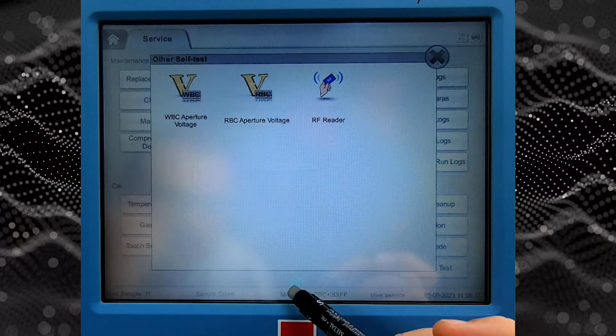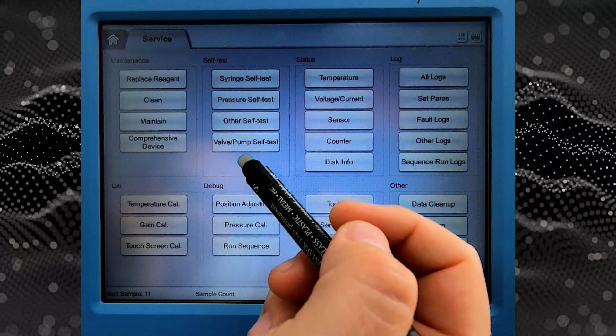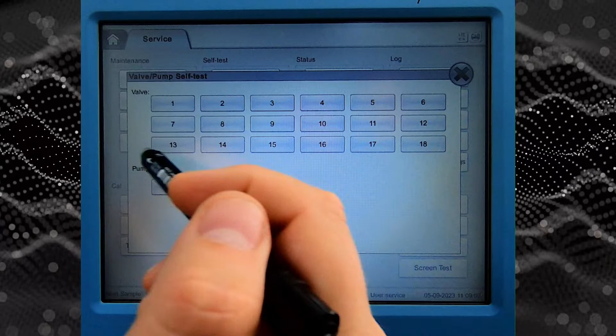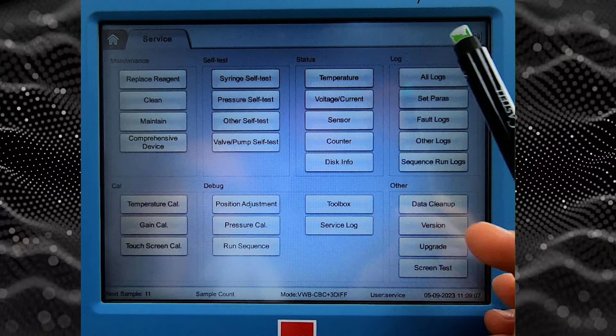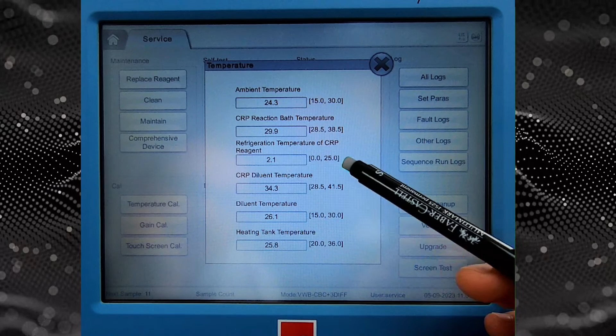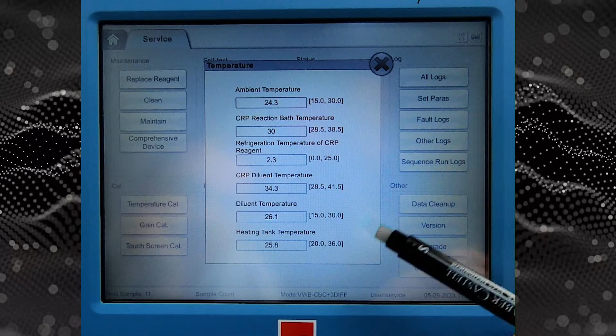We can also test the WBC, RBC voltages. So it's saying WBC or RBC voltage is normal, so it's not showing you the voltage level. Valve pump, so that's valves and pumps. That's it. I just press unlock. In temperatures, the analyzer is showing you the temperatures: ambient, CRP reaction bath 29, refrigerator for CRP, diluent 34, right? Diluent temperature, heating temperature.